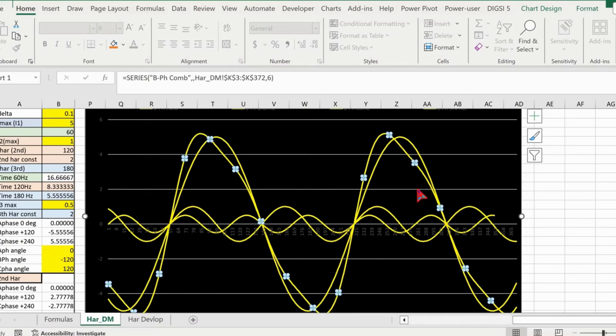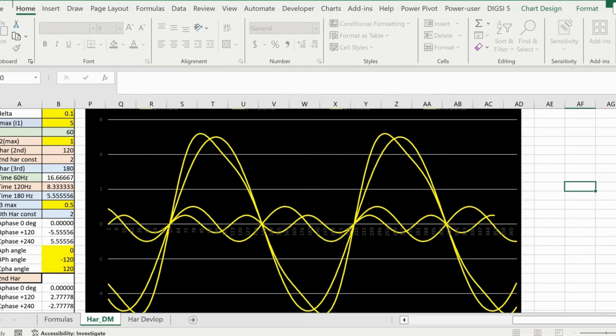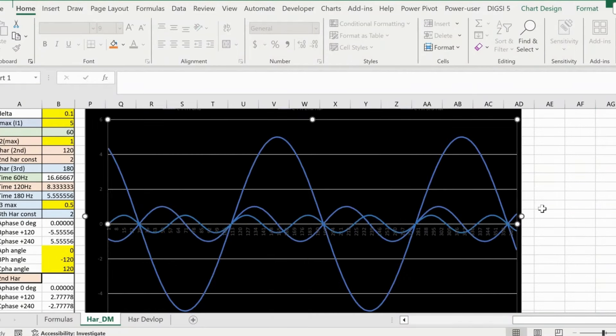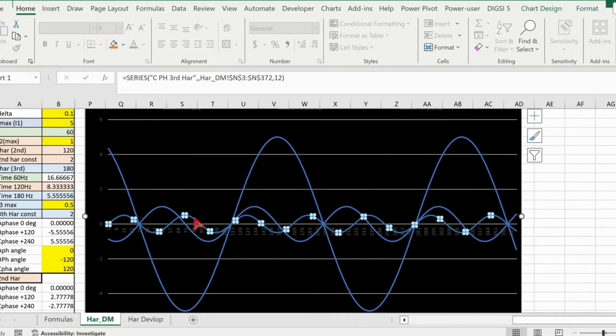It's very important that the waveform shape of all three phases is correct, otherwise the relay will mal-operate for a different phase combination. We will see the most common mistakes when a relay test kit generates harmonic waveforms, and how incorrect phase angles influence relay mal-operation or cause wrong measurement by the relay algorithm. Let's move on to C-phase — I'll uncheck all A and B phase signals, then enable C-phase fundamental, second harmonic, and third harmonic.